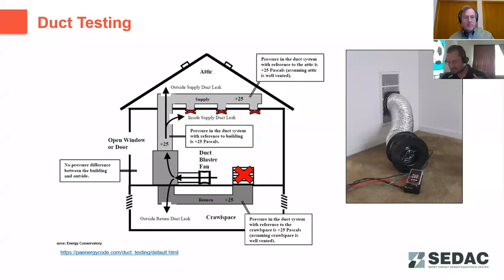For the rough-in test, duct leakage should be less than or equal to 4 cubic feet per minute per 100 square feet of conditioned floor area. If you're doing that rough-in test before the furnace is installed to the ductwork, you'll test the supply ductwork, then the return ductwork, add those 2 results together, and that result should be less than or equal to 3 cubic feet per minute per 100 square feet of floor area. If you're doing the post-construction test, that furnace is going to be in place, and that requirement is, again, that 4 cubic feet per minute per 100 square feet.